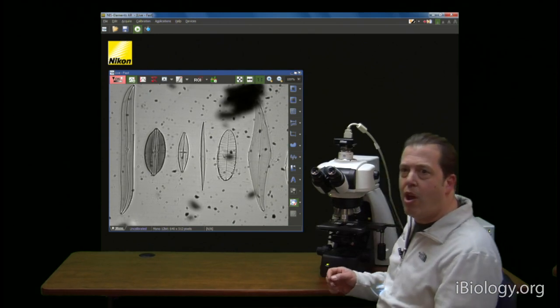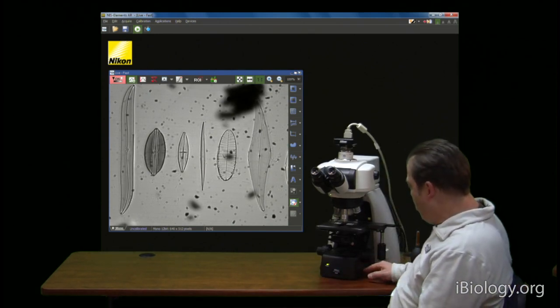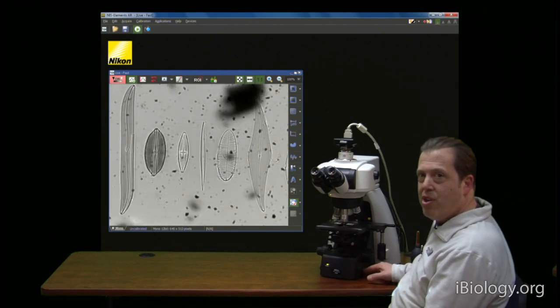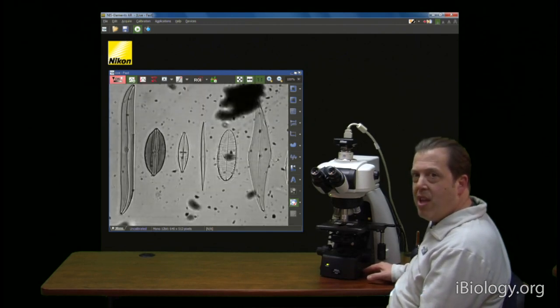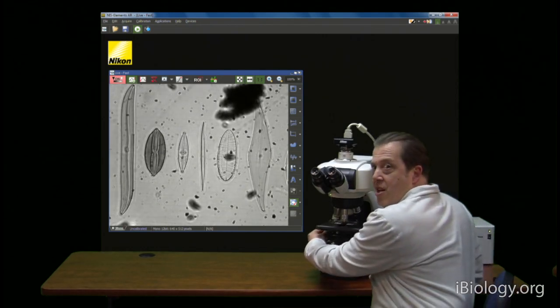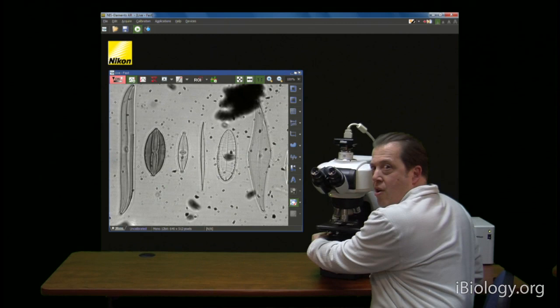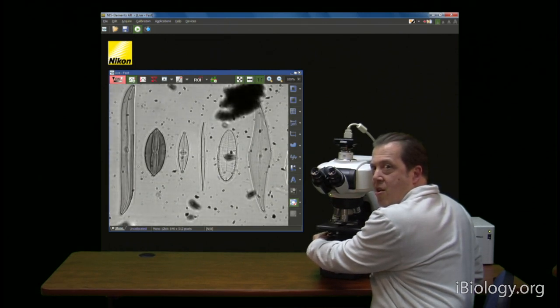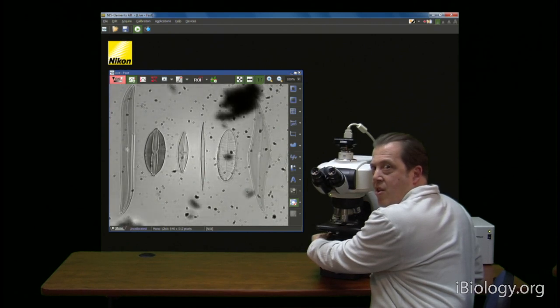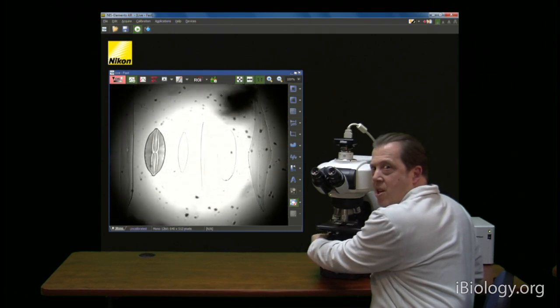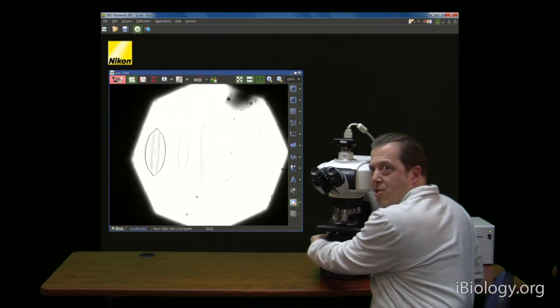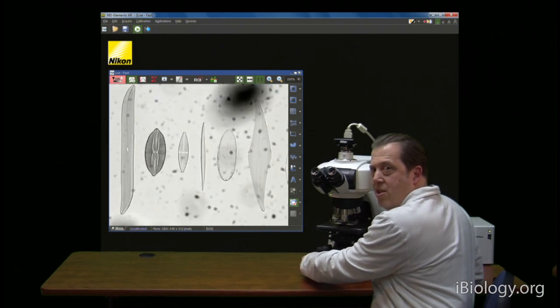So let's see if we're in Köhler alignment. We'll do that by closing down our field aperture. Generally what we want to do is make sure that the field aperture is centered and in focus, meaning that our condenser is in proper focus. So let's adjust this condenser here with that closed field aperture. You can see it was not in focus, coming closer, closer and there we have sharp focus of the field aperture. Looks reasonably centered so let's just open that up right outside our field of view and adjust our light.